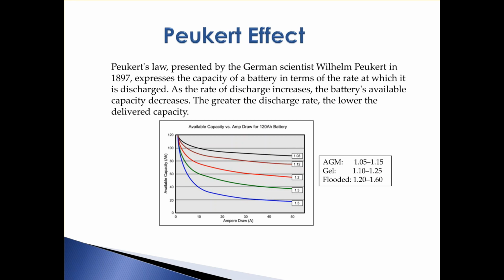And now, as you pull more and more current out of the battery, you'll find that it gives you less and less total capacity. The top numbers, 1.08, something for an AGM battery, and maybe down to the 1.12. The ones in the middle would be for a gel cell, and the ones at the very bottom would be for a flooded wet acid battery. So you can see, with a really not very good flooded battery, if you pulled 50 amps out of the battery, instead of getting over 2 hours that you would expect from a 120 amp hour battery, you're only going to get about 20 amp hours out of it.